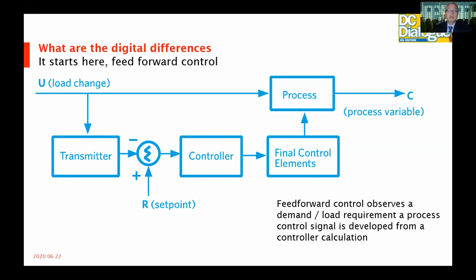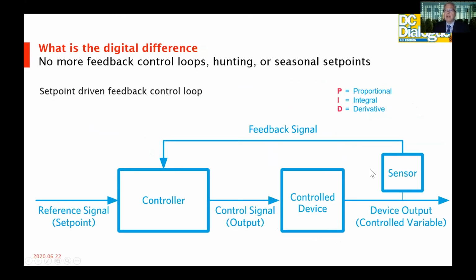So what's different about it? Well, it all starts with this. It's a method of control. It's called feed-forward control, where we observe a load change, a requirement, whether it's water flow or airflow or some requirement changes, maybe a valve opens in response to another controller. And there's a predetermined response for the process. It's a control map. It's you do this, I do that, and then the process controller changes and the process variable changes. So it's very unlike traditional control, which is a feedback control method.